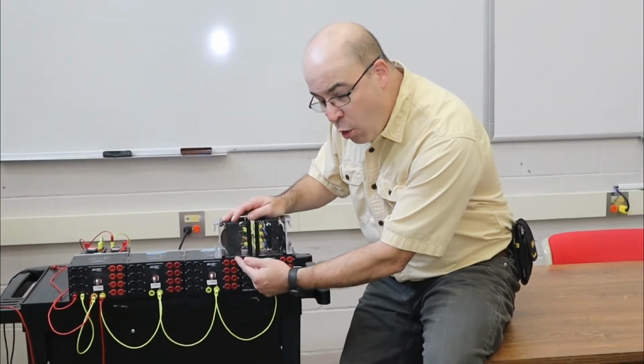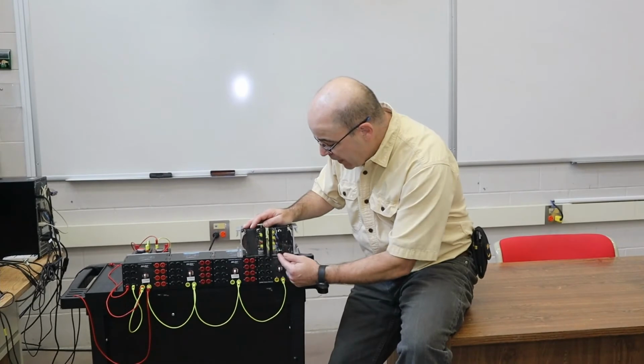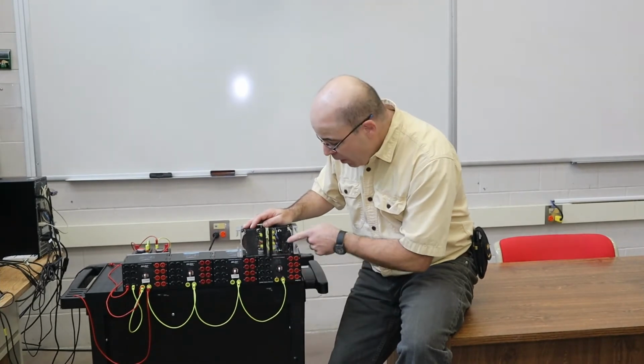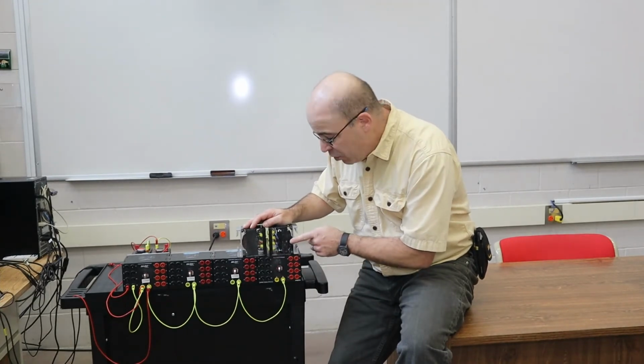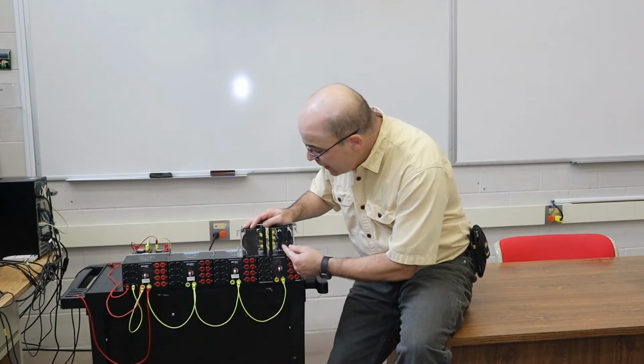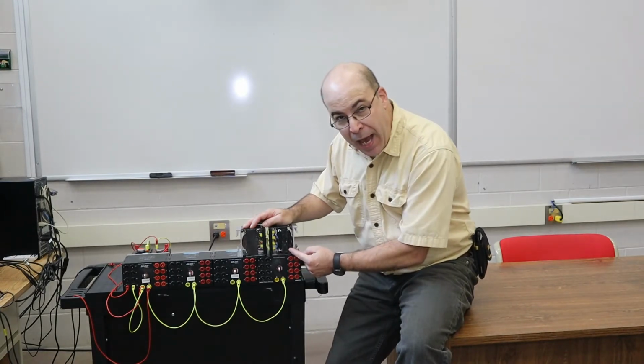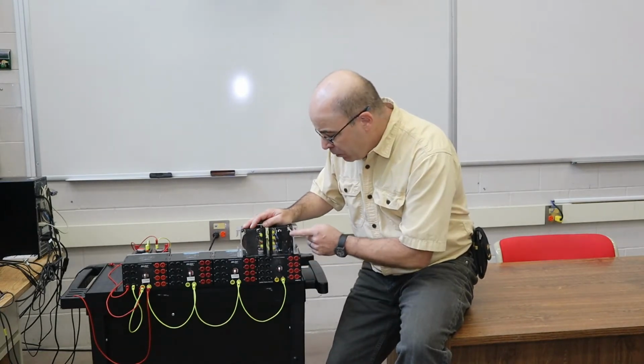It's that the core of each of these transformers is significantly different. The smaller VA transformer at 25 VA, we can see that the core is roughly half as wide. This relates to the amount of power output that the transformer can give us in our control circuit.